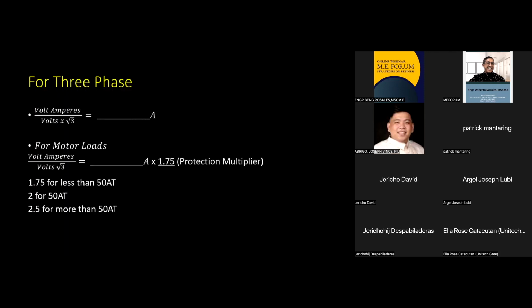What is the purpose of the neutral? The purpose of neutral is to collect or to absorb unbalanced voltage or current in the system. Now, if I continue with the slide, for 3-phase calculation, it is volt-amperes divided by volts times the square root of 3. The square root of 3, or 1.732, basically came from trigonometry. I won't derive that, but it is based on the PEC as well. So basically, for motor loads, the apparent power, volt-ampere, divided by volts times square root of 3, is equal to the motor load times the protection multiplier for our system.